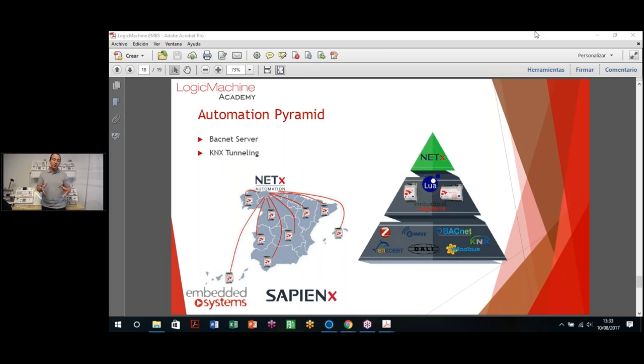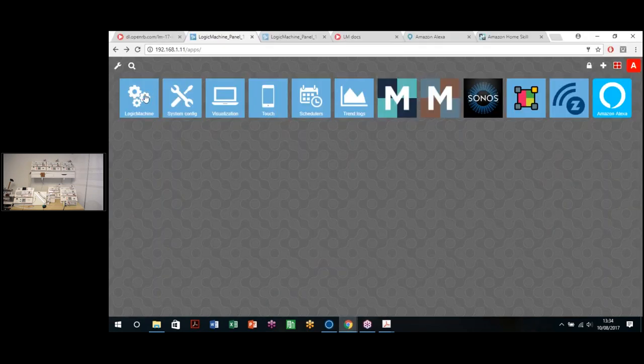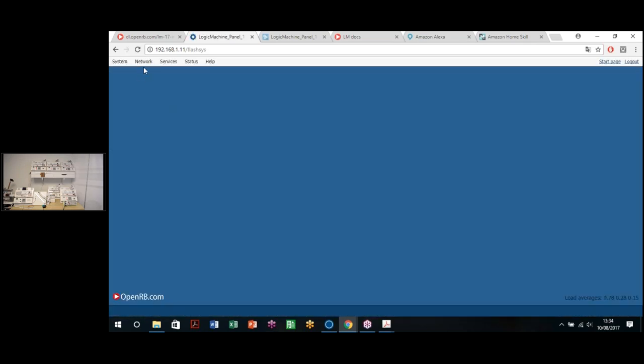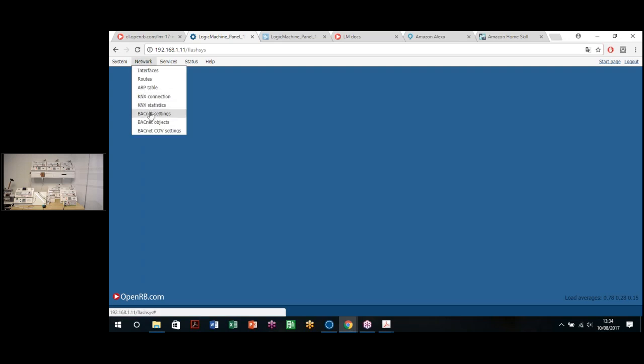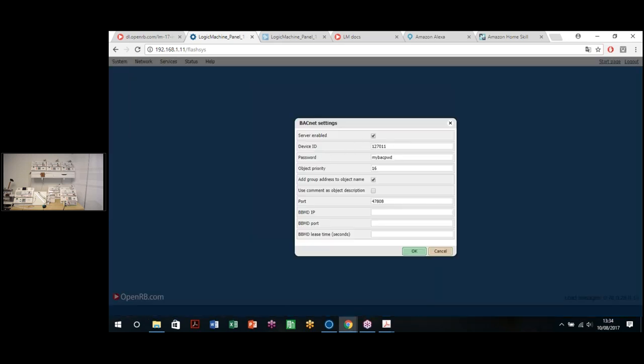We are going to use the NetX Automation BMS server that we consider the best option for this integration, as it does not depend on any manufacturer. So in this case, we have a lot of logic machines. I guess here we can find panel one logic machine. And about BACnet, what we can do is just check if BACnet is activated in the BACnet settings. The server has to be enabled. Okay, I am enabling the server.